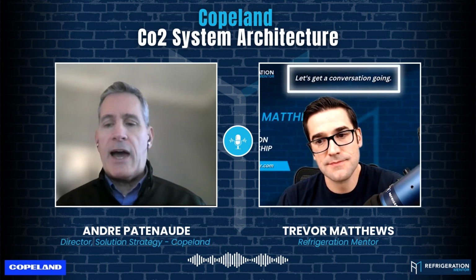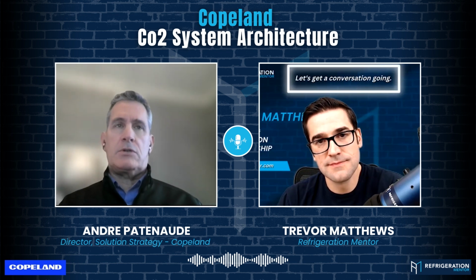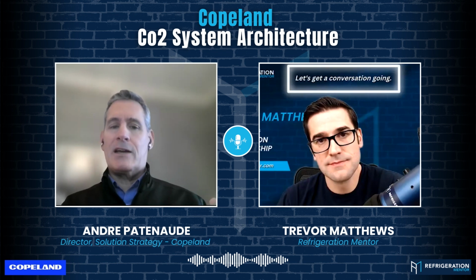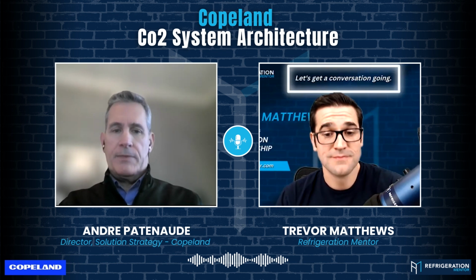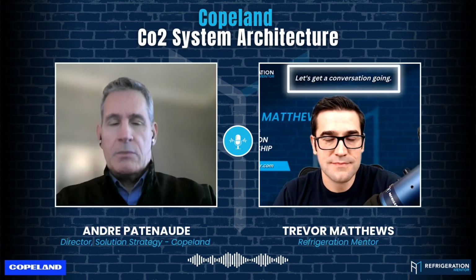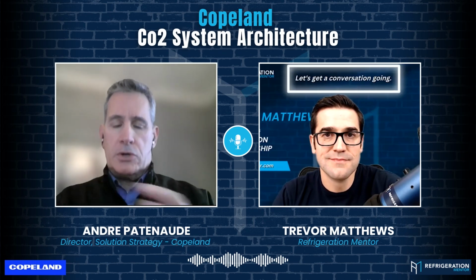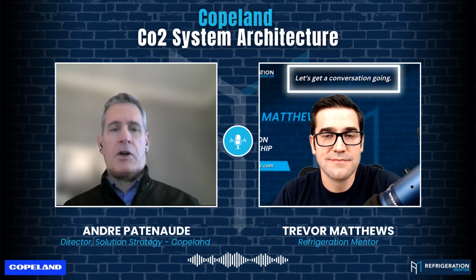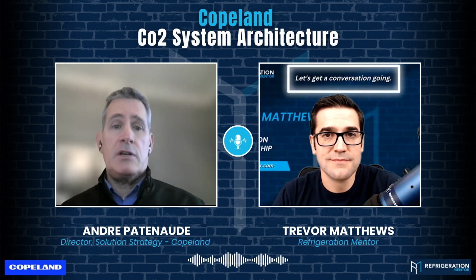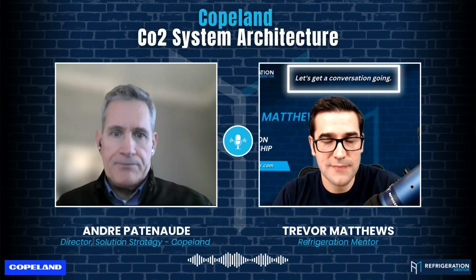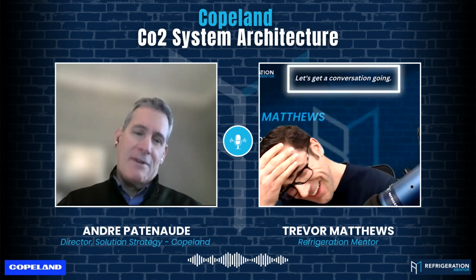So they know they have to. The thing they really need to ask themselves if they want to go to CO2 is: where exactly is this store located that I'm thinking of, or these several stores, and how does the climate impact that technology? Because we know CO2 in its basic system architecture is quite efficient in a low ambient area. In Canada, for example, most of it sees 90% of operating hours below 60 Fahrenheit. That other 10%, depending...